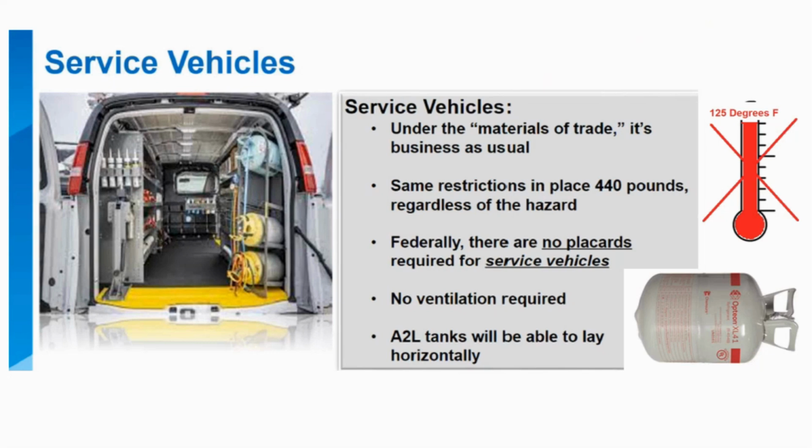However, when you're carrying the tanks, it is going to be a little bit different in that because we have that relief valve, if it were to relieve, we need it to relieve gas. Remember earlier I said the time it's most flammable is when we're changing from liquid to gas. So if we're relieving liquid, it's going to evaporate, and at that point is when it is most flammable. So we want to make sure that relief valve relieves gas. So we're either going to store the tanks upright, or if you're using a racking system, like shown here, we just want to make sure that the relief valve is at the top of the tank. So if for some reason it would relieve, once again, it's going to relieve the gas, not the liquid portion of it. So we always have to make sure that relief valve is at the top of the cylinder when we're laying it horizontally.